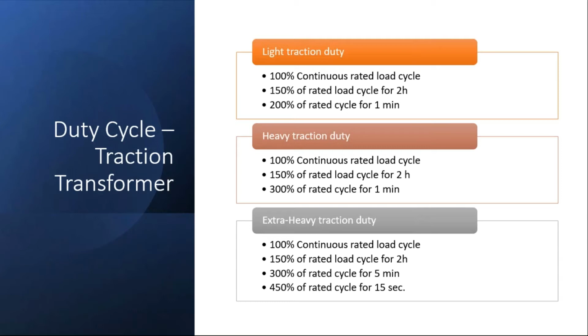Most of these transformers are connected to a very low voltage rectifier, which is mostly 500, 600 volts, less than 1,000 volts for sure. They have a tendency of having short circuits or heavy load, which is equivalent to short circuit. That's the reason they go through short circuit testing. A lot of these transit customers want the transformer to be robust. Nobody wants to get delayed going to work because a transformer failed. So there is a lot more requirement than the design and all the standard calls for.